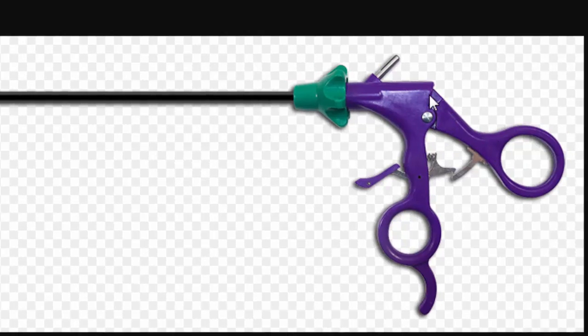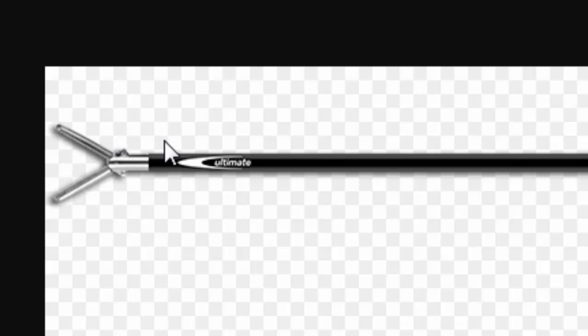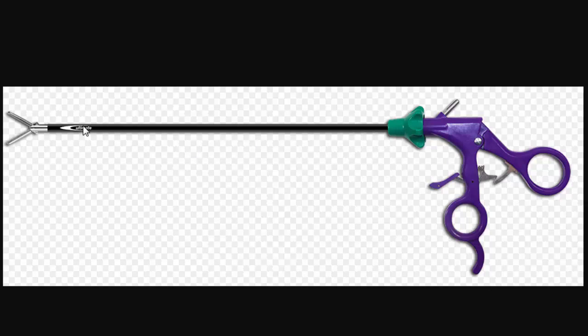This scissors actuator pushes a rod which moves these two paddles that can clamp on tissue in the body. The interesting bit here is you have a post attached to an electrosurgical unit that transmits electrical energy down this shaft to these paddles. You need to have this shaft insulated for that purpose because you only want the electricity sent to the patient through what you can see in this area, and it needs to be insulated for many safety reasons. We have shrink tube over a metal shaft.